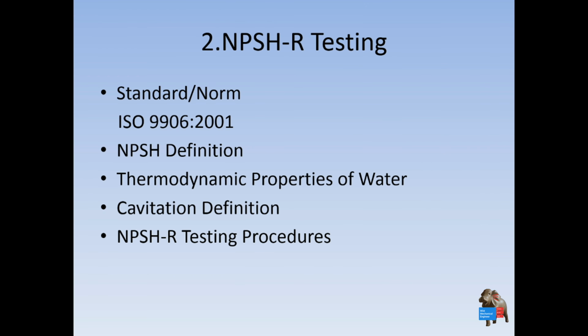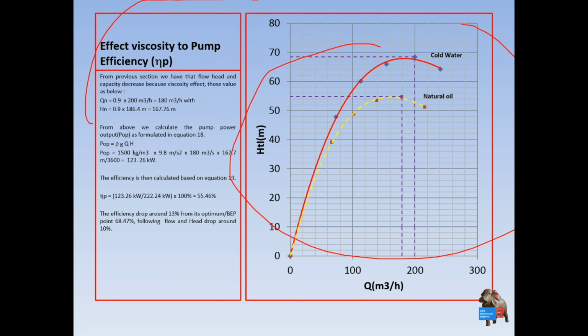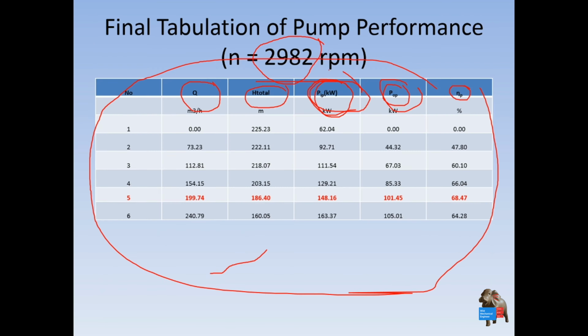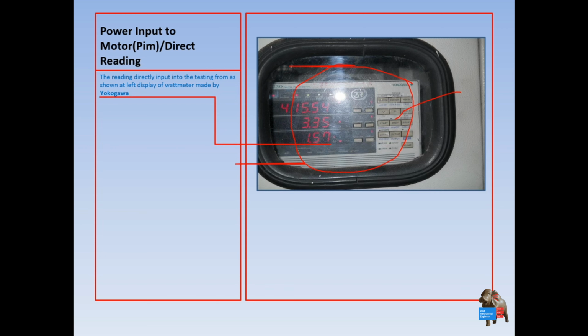Okay. So that's all. To summarize this presentation, I would like to repeat again. Before you want to understand how the pump is tested, you have to understand the energy transfer in the system. Electric energy is transferred to the AC motor. The AC motor converts electric energy into mechanical energy, the shaft rotation. The motor shaft is coupled to the pump shaft, and the pump shaft rotates and transfers the energy into the impellers, and the impellers of the pump transfer the energy to the water.